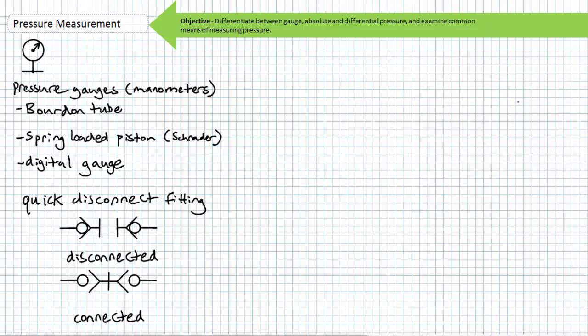Analog pressure gauges are those gauges that display the pressure reading on a dial or a vertical scale with a needle similar to the hand of a clock or the height of a liquid in a thermometer. Given the subjective nature of the analog scale, there will be room for interpretation and inexactness. In contrast, a digital pressure gauge displays an exact numerical pressure reading in the desired units with no room for subjective interpretation. Digital pressure gauges sometimes include additional features like data logging and transmission capabilities. Digital pressure gauges obviously include more hardware, necessitate electrical power, and are more expensive than analog gauges.